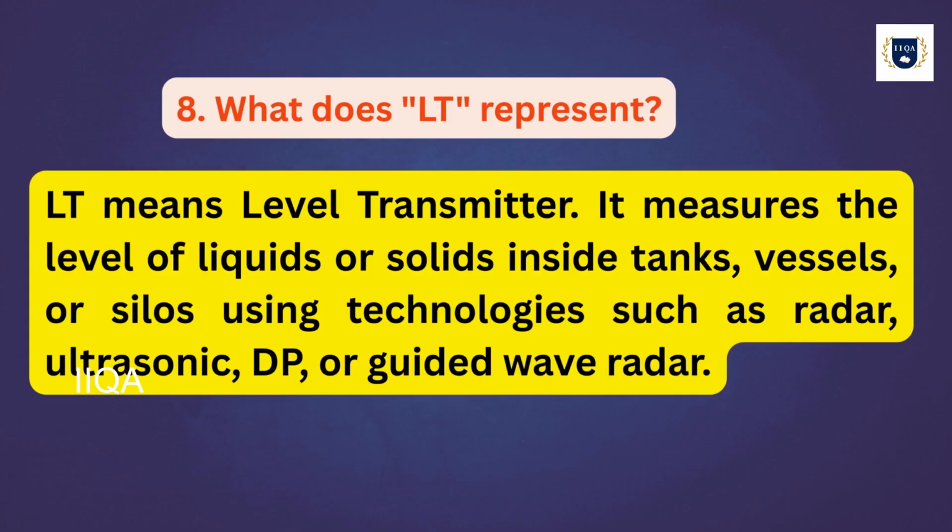What does LT represent? LT means level transmitter. It measures the level of liquids or solids inside tanks, vessels, or silos using technologies such as radar, ultrasonic, DP, or guided wave radar.